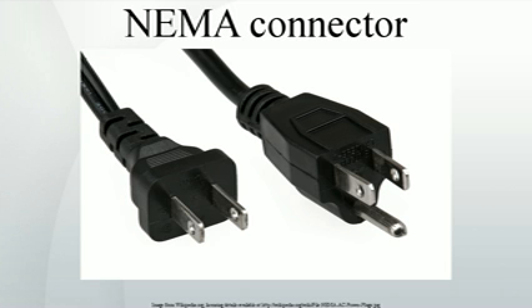Since January 1, 1974, all new power outlets are required to have a ground connection, using grounded sockets, typically NEMA 5-15 or NEMA 5-20, that accept both grounded and non-grounded plugs. Replacement of obsolete NEMA 1 receptacles requires either a NEMA 5, for two conductors plus ground wire configurations, or a NEMA 5 GFCI for two-wire non-grounded configurations, when a ground conductor is not available.